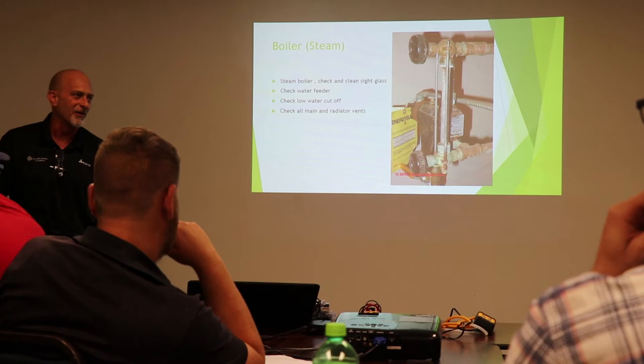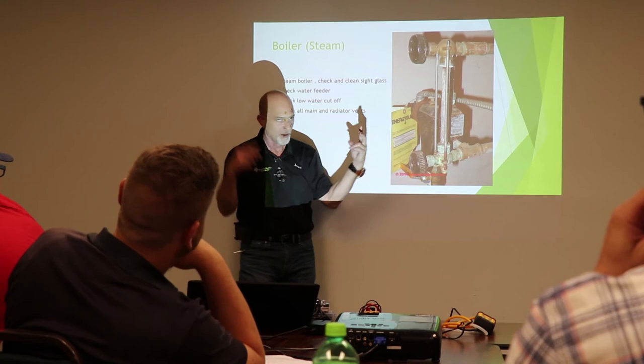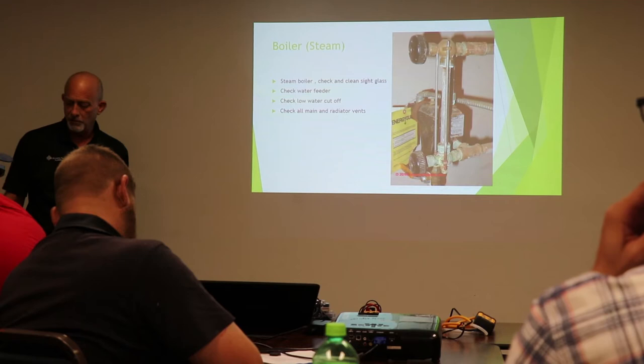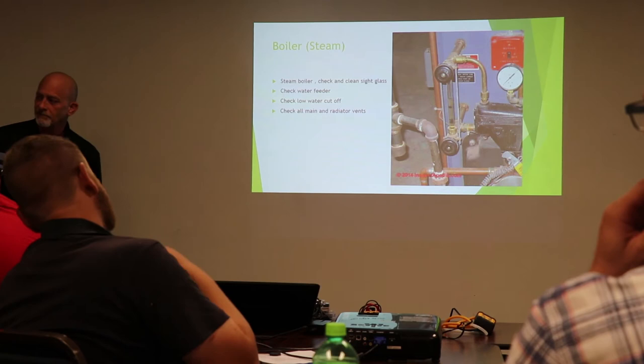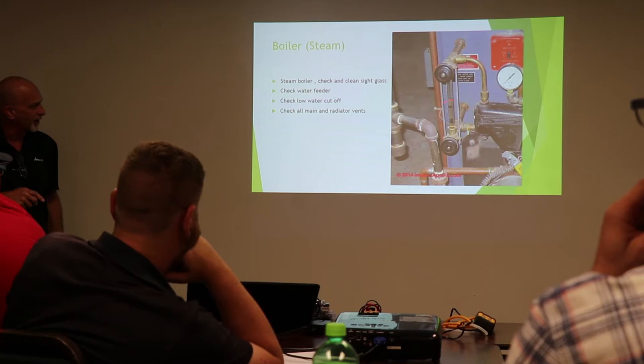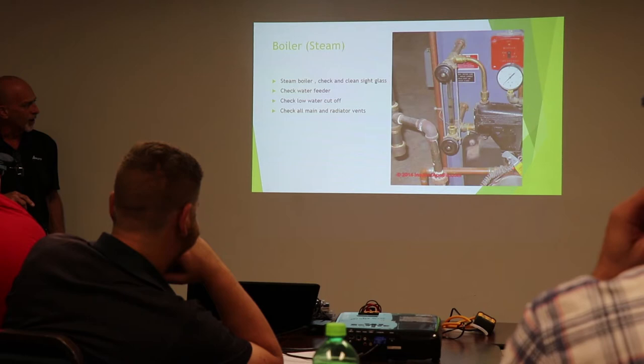You're also going to get two new seals. So once we do get our sight glass to the right length, we put our locking nuts on there, put our new seals on there, set it into place, tighten them down, we're good to go. Fill it back up with water, and it should look similar to that. Okay, we can see the water in the boiler. See our water line right here. This here, our low water cutoff, and a dump valve here.